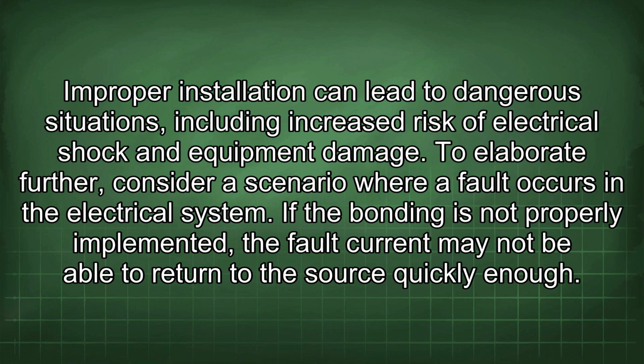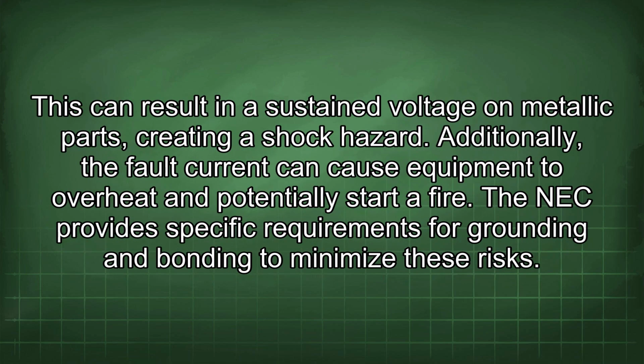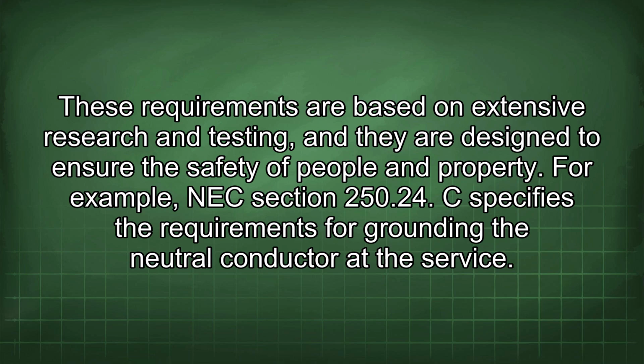To elaborate further, consider a scenario where a fault occurs in the electrical system. If the bonding is not properly implemented, the fault current may not be able to return to the source quickly enough. This can result in a sustained voltage on metallic parts, creating a shock hazard. Additionally, the fault current can cause equipment to overheat and potentially start a fire. The NEC provides specific requirements for grounding and bonding to minimize these risks. These requirements are based on extensive research and testing, and they are designed to ensure the safety of people and property.